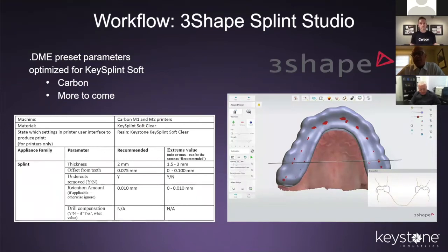We've worked with Carbon as well as 3Shape, which is the design software that Micro would use in designing this. So you would send over your intraoral scan to them. They would design it in 3Shape, and 3Shape has an automatic drop down for the Carbon technology. This optimizes the material to the particular printer being used. As there are so many different printers out there, the settings on each one would be unique. So we've spent a lot of time in what we call validation with Carbon to ensure that the settings they're using when printing this material give you the best quality product possible off of the printer.